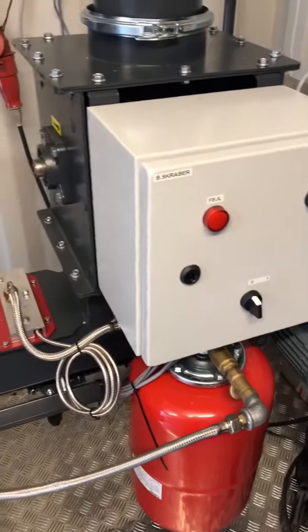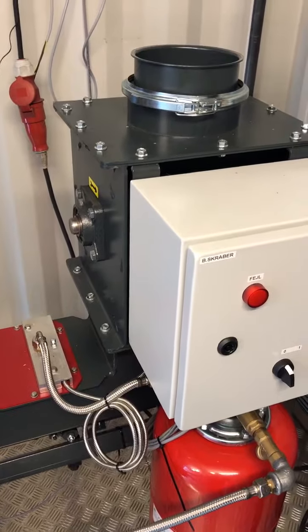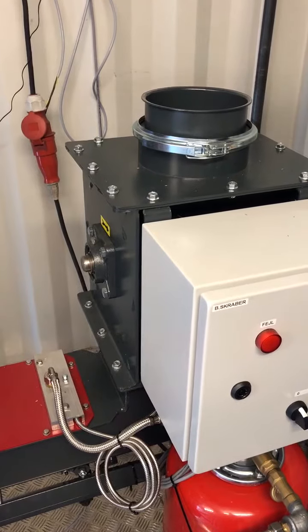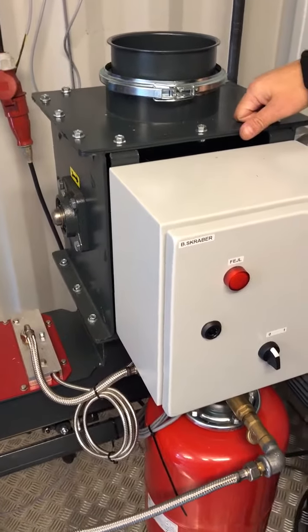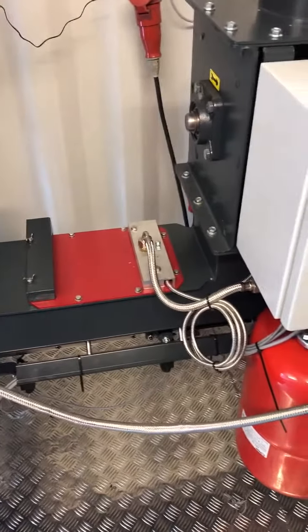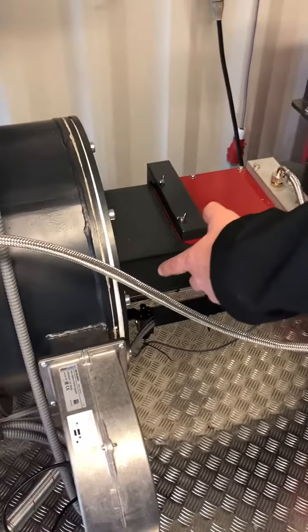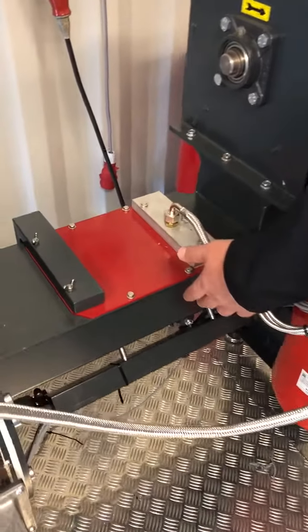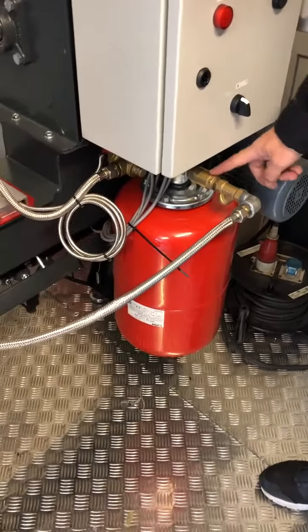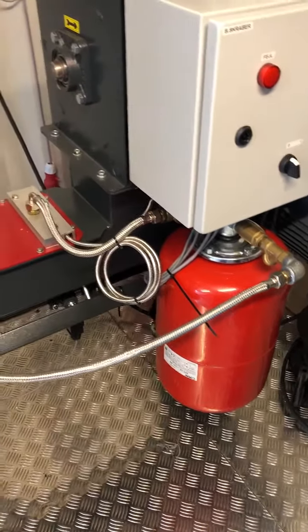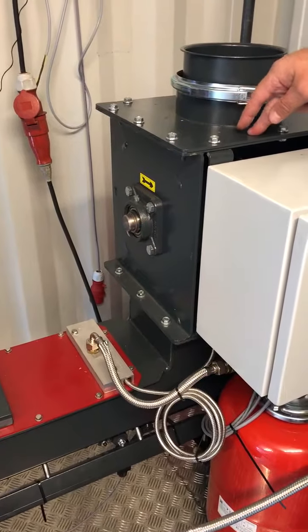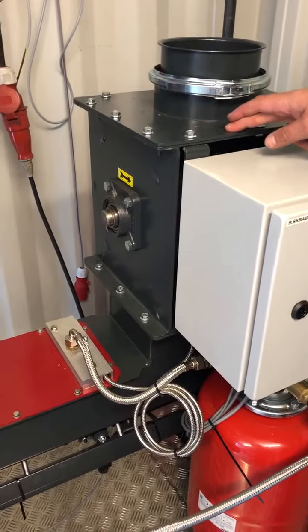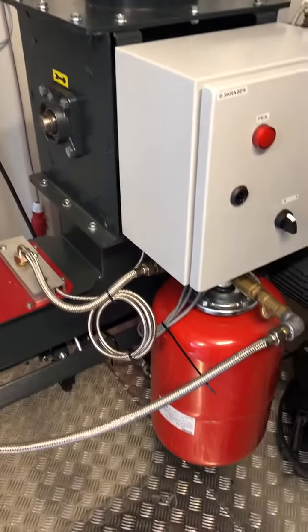When you do the startup and the rotating auger or whatever delivering the fuel, when it stops, the rotor valve and the stoker auger runs an after run. Depends on what model it is, but on the CS model it's 25 seconds to run it empty. So it pushes all the fuel into the burner tube, so there's no risk for backburn. Even though we've got a sprinkler system with an expansion tank, so if the water pressure is away, we've got a control valve here, so there's always water pressure on the tank. The rotor valve also functions as a backburn protection. So we've got 2, plus we run empty each time.